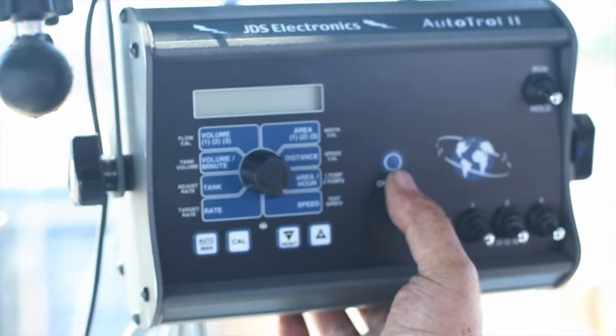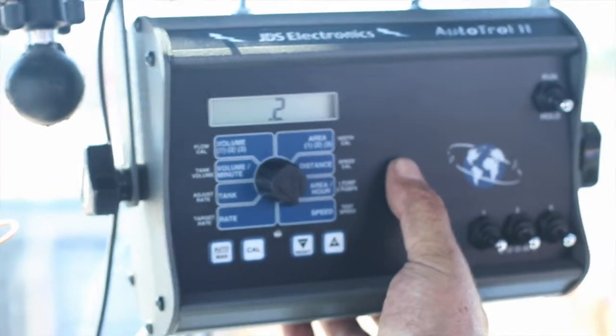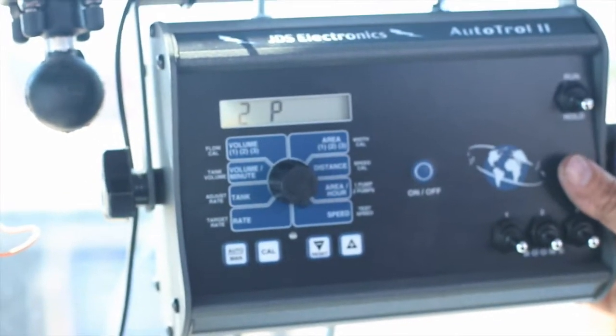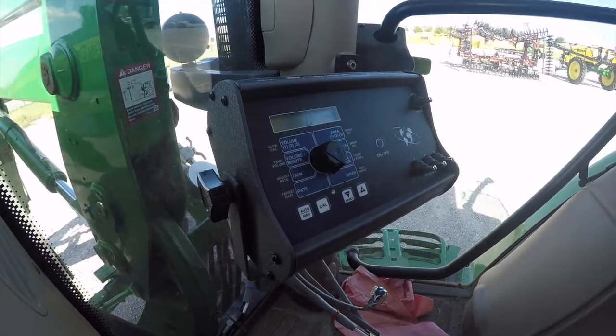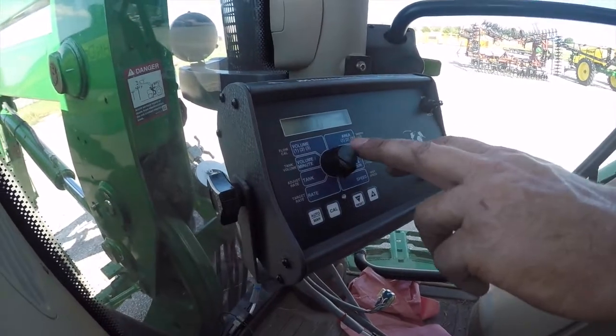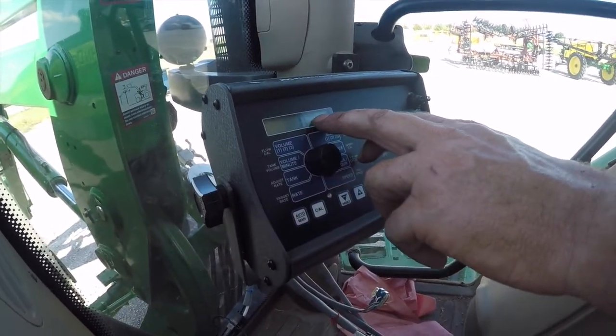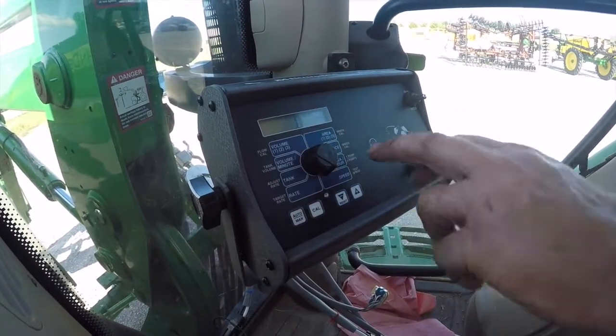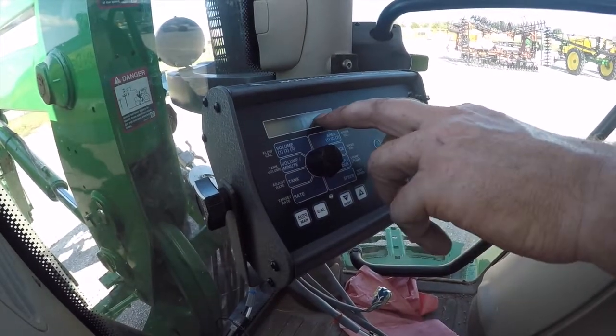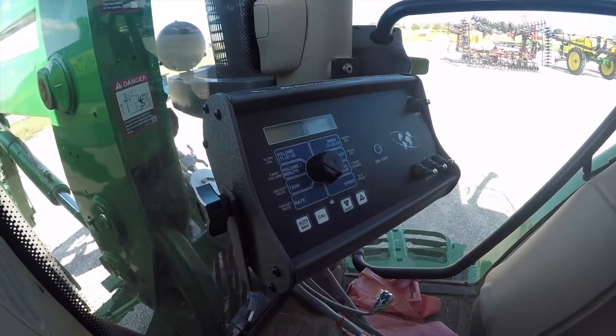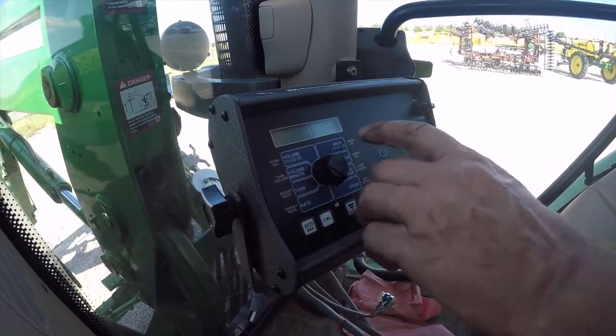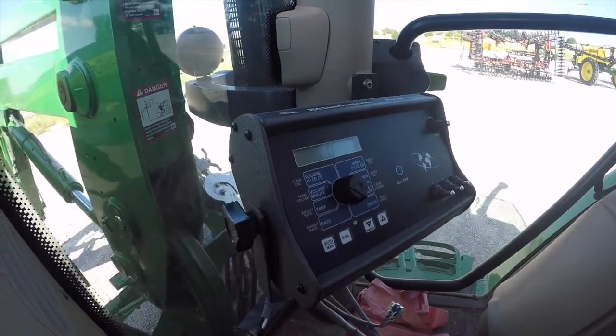The first thing you do on a brand new Autotrol is you turn it on, and you have a bunch of numbers that show up, factory numbers, and then you also see a number saying 2P. Now that's programmed for 2 pumps. You will also see it says 0.0 manual hold. Now the controller always needs to be on auto, so we will switch that to auto.